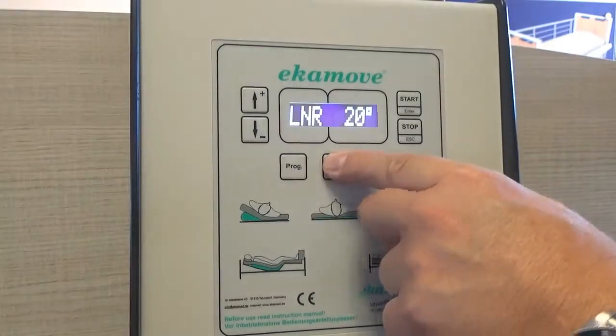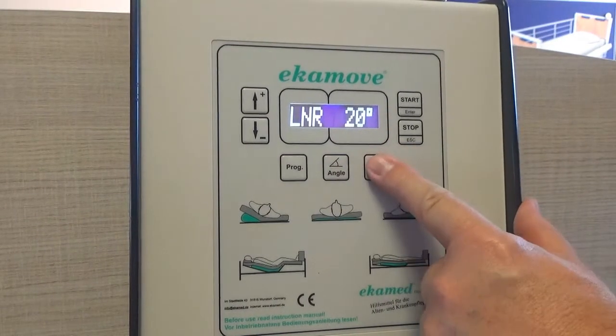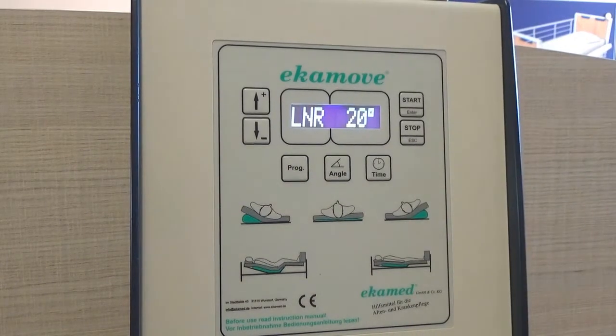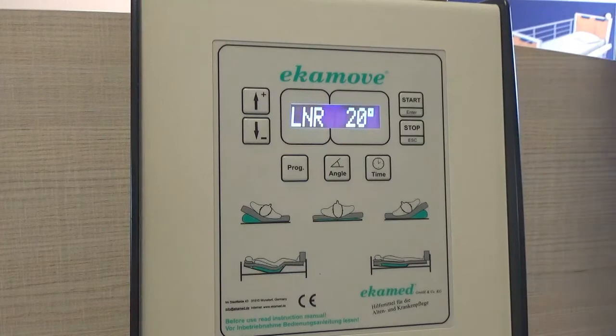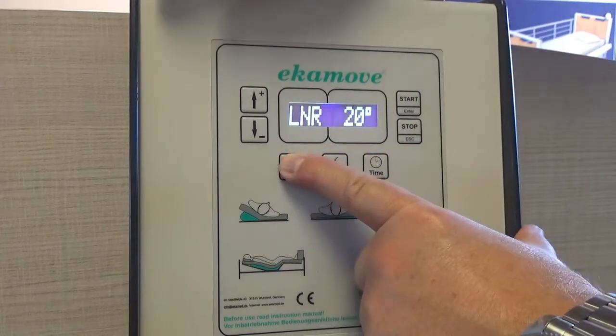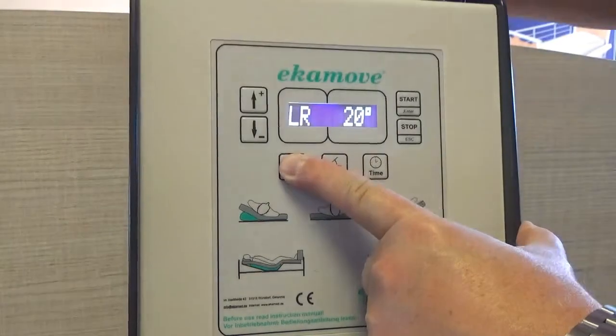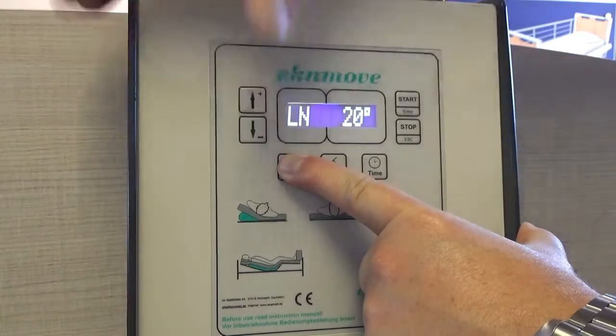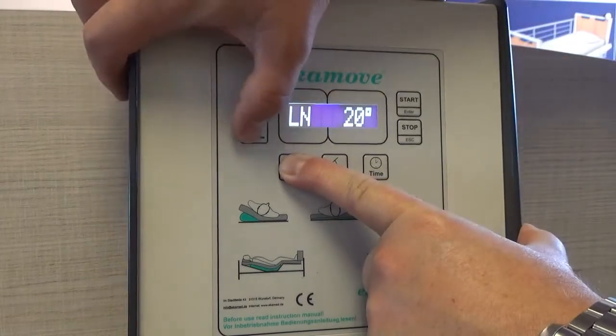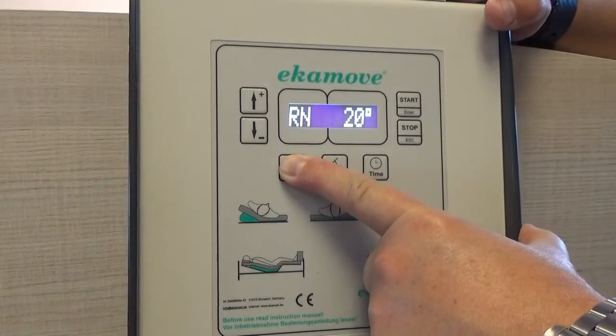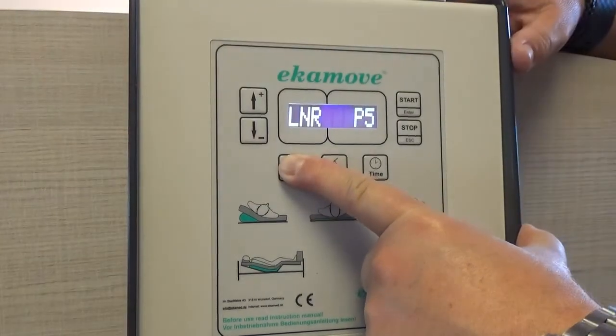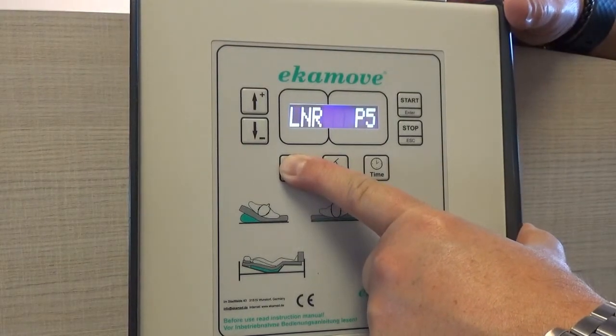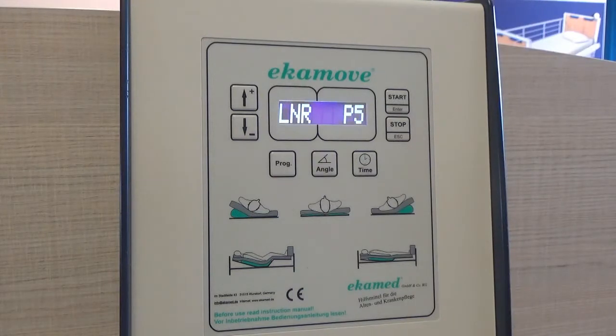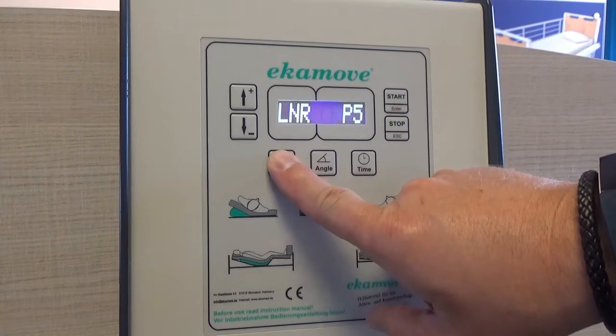Once calibration is complete, the screen displays the standard factory settings, LNR, meaning left, neutral, right, 20 degrees, 20 mins. Other program options are LR, left and right turns, eliminating neutral; LN, left turn and neutral, eliminating right; RN, right turn and neutral, eliminating left; P5, specialist program for complex needs. Select the program you want to use.